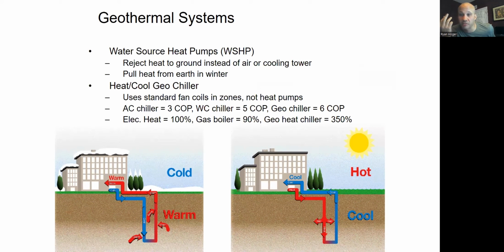And that's really expensive. It might be better just to pay for the 10 wells, the baseline, and then have a small boiler tempering the rest of the way, right? Or a cooling tower if the problem was the opposite way. But yeah, you can just keep making the geo field bigger and bigger until, instead of heating the ground up a couple degrees a year, plus a couple degrees the next year, and a couple degrees the next year, you're heating it up tenths of a degree over the course of a decade, and it doesn't matter then.